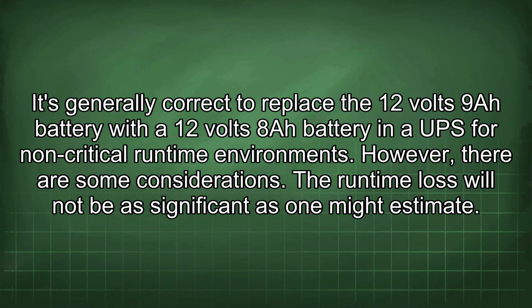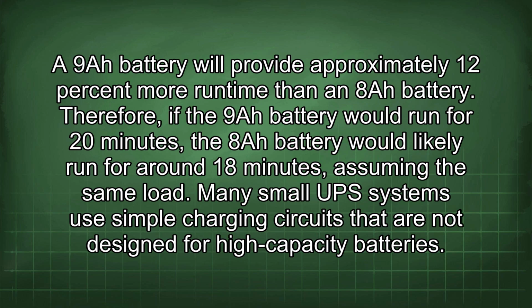It's generally correct to replace the 12 volts 9 Ah battery with the 12 volts 8 Ah battery in a UPS for non-critical runtime environments. However, there are some considerations. The runtime loss will not be as significant as one might estimate. A 9 Ah battery will provide approximately 12% more runtime than an 8 Ah battery. Therefore, if the 9 Ah battery would run for 20 minutes, the 8 Ah battery would likely run for around 18 minutes, assuming the same load.